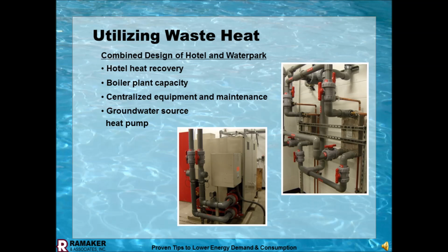Right now we have a project. In the past, a lot of our projects had gas-fired air handling units. This particular project, we went with a central boiler plant, and we're using a hot water loop to heat the pools, heat the buildings, and also heat the air handling unit for the water park.